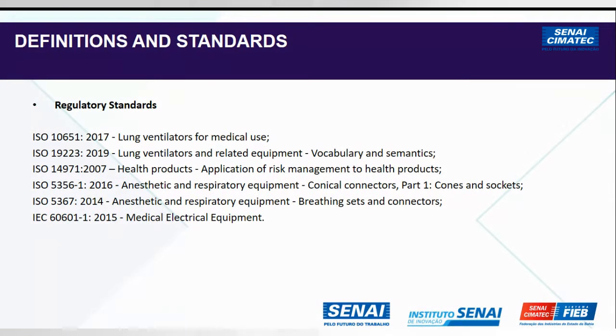We have many regulatory standards for ventilators. The common regulatory standards are the lung ventilators for medical use 10651, and the lung ventilators and related equipment 19223. The health products 14971, and 5356 and 5367 for anesthetic and respiratory equipment. The anesthetic equipment uses a mechanical ventilator in its process because they are together in the same rule. And then the general rule for medical ventilators is 60601-1, medical electrical equipment.